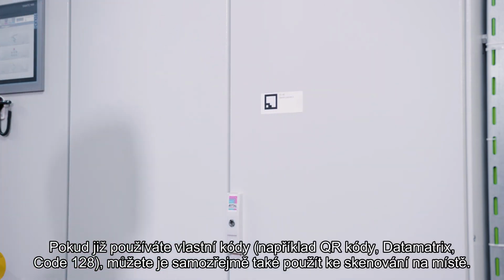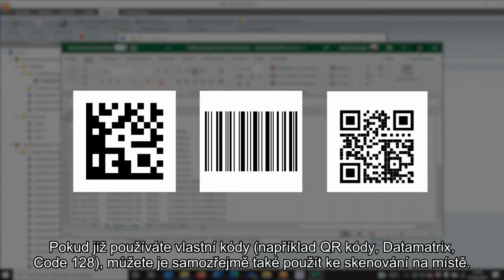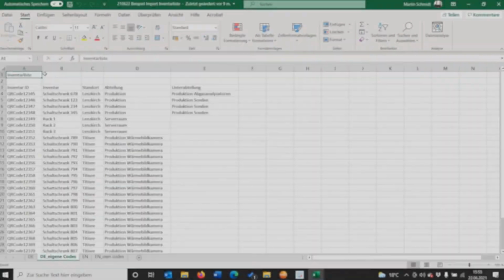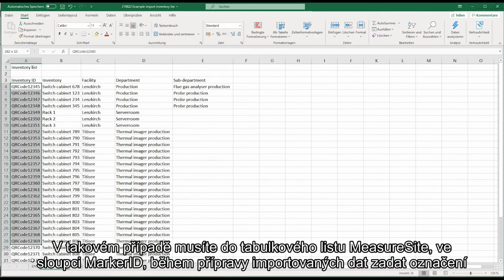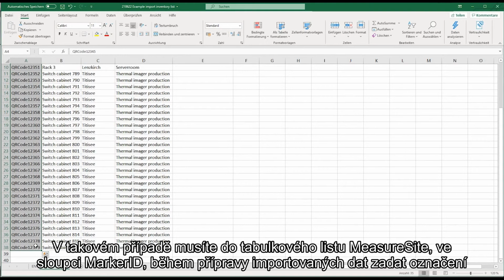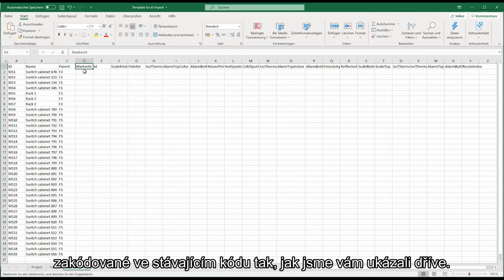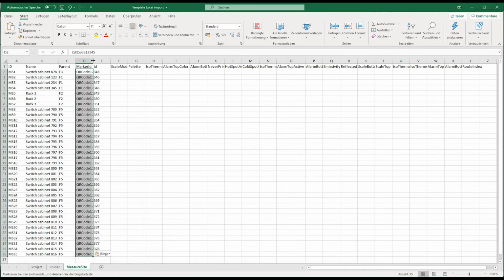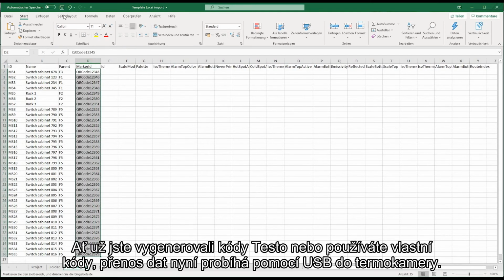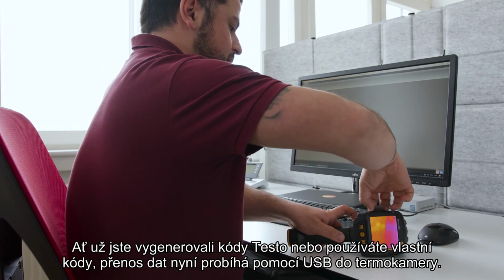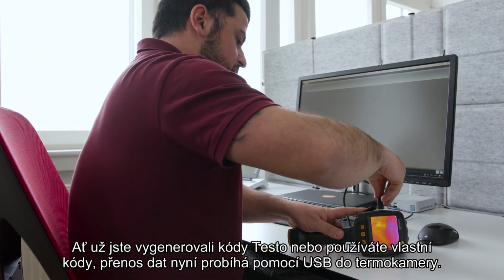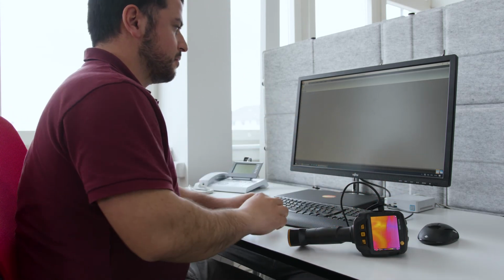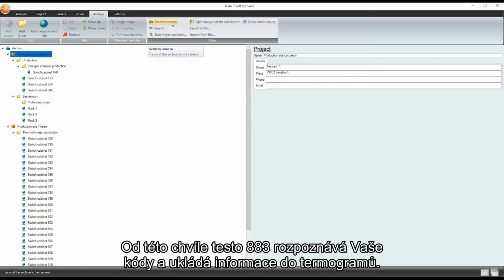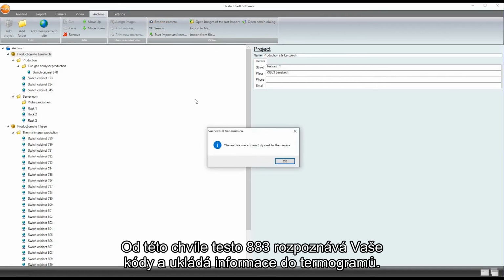If you already have your own codes in use, for example, QR codes, data matrix, code 128, you can of course also use these to scan on site. In this case, you have to enter the name encoded by the existing code into the table sheet Measure site in the column Marker ID during the preparation of the import data as we showed you earlier. Whether you've generated Testo codes or are using your own codes, the transfer of the data now takes place by USB to the thermal imager. From now on, the Testo 883 recognizes your codes and saves the information in the thermal images.